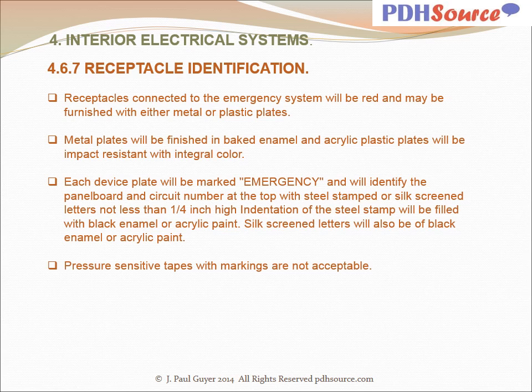Receptacles connected to the emergency system will be red and may be furnished with either metal or plastic plates. Metal plates will be finished in baked enamel and acrylic plastic plates will be impact resistant with integral color. Each device plate will be marked emergency and will identify the panel board and circuit number at the top with steel stamped or silk screened letters not less than 1/4 inch high. Indentation of the steel stamp will be filled with black enamel or acrylic paint. Silk screened letters will also be of black enamel or acrylic paint. Pressure sensitive tapes with markings are not acceptable.